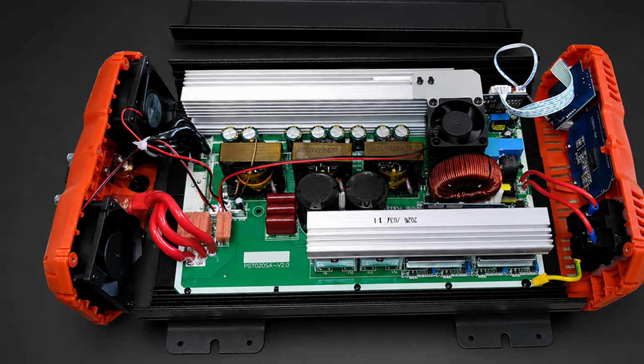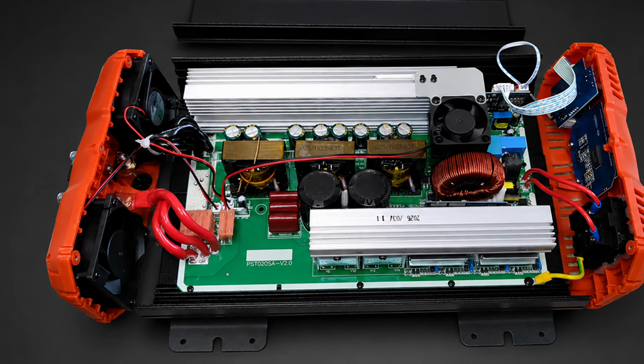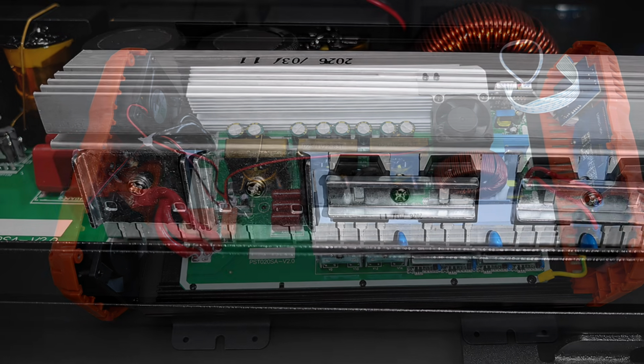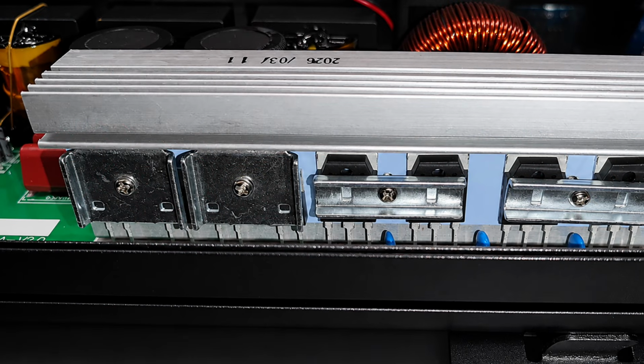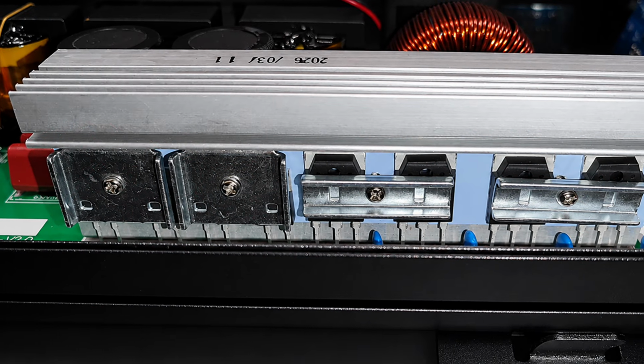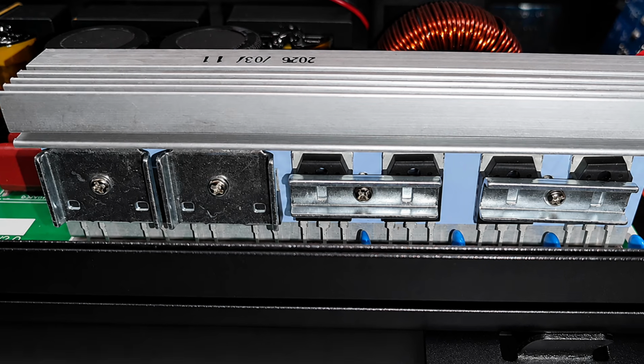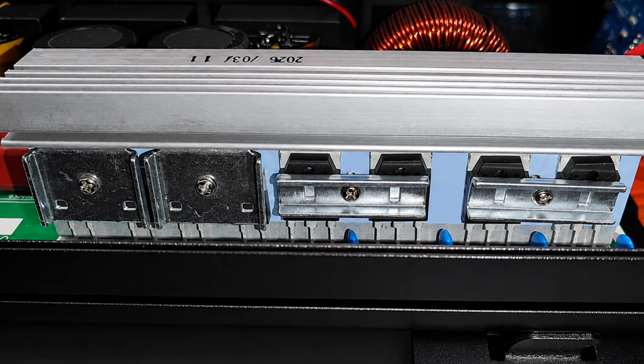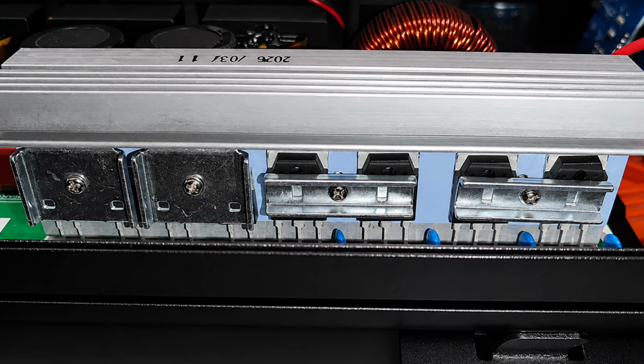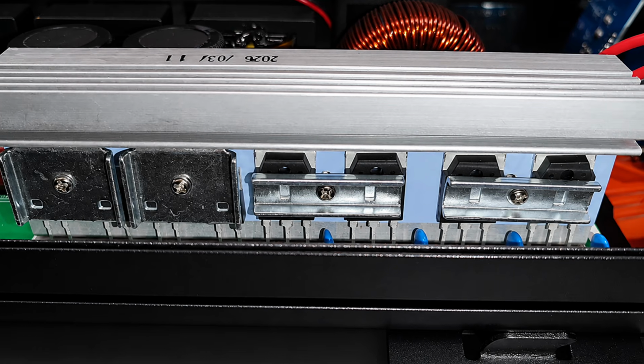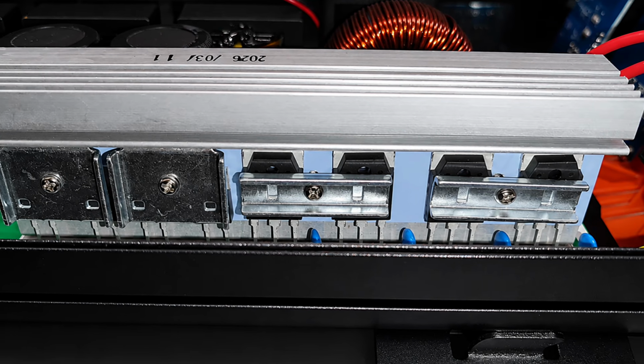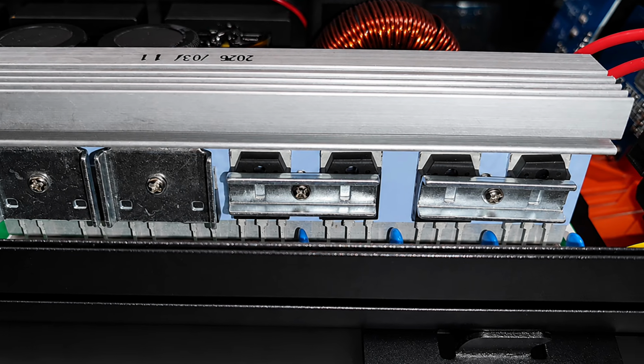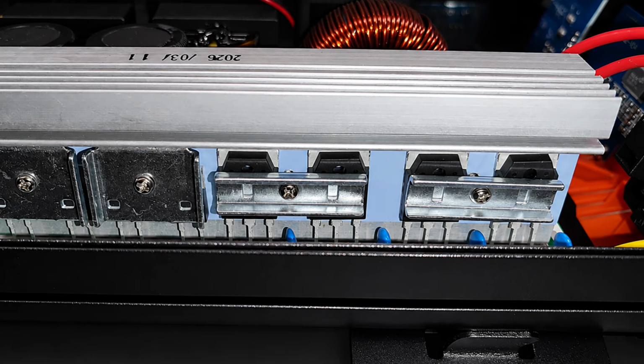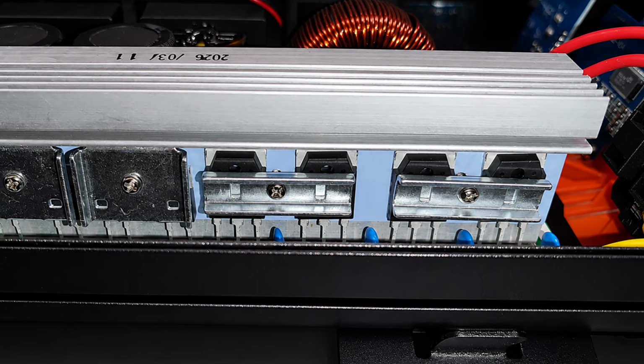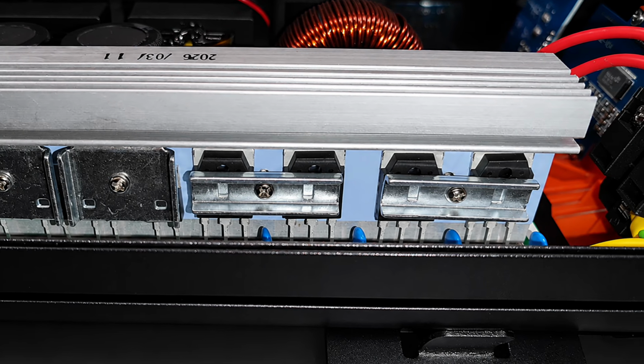The production date is visible on the heatsink, March 11, 2026. The main power components are pressed against the aluminum heatsink with metal bars. Some of the elements are covered by the fasteners, so the markings cannot be read without full disassembly. The layout shows several parallel groups of power switches. For a 12-volt, 2-kilowatt inverter, this is expected. The input currents are high, and they need to be distributed among several elements.